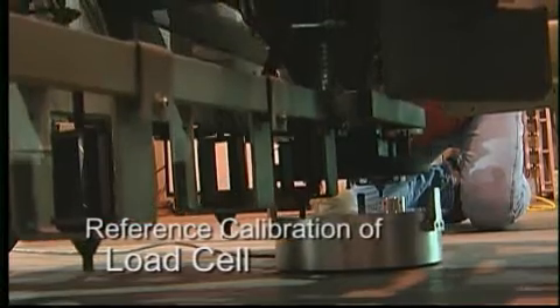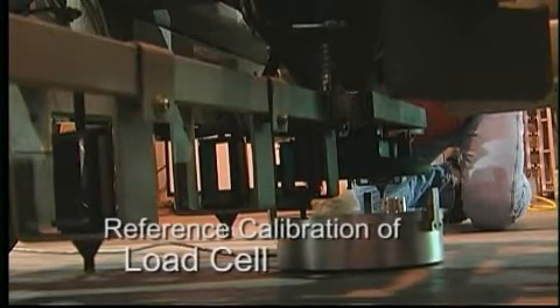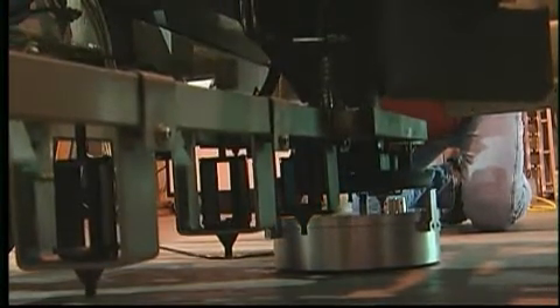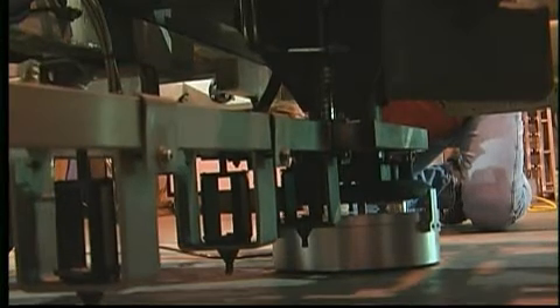The first step of load cell calibration is to make sure that the reference load cell is in line with the FWD load cell. This has to be done manually.